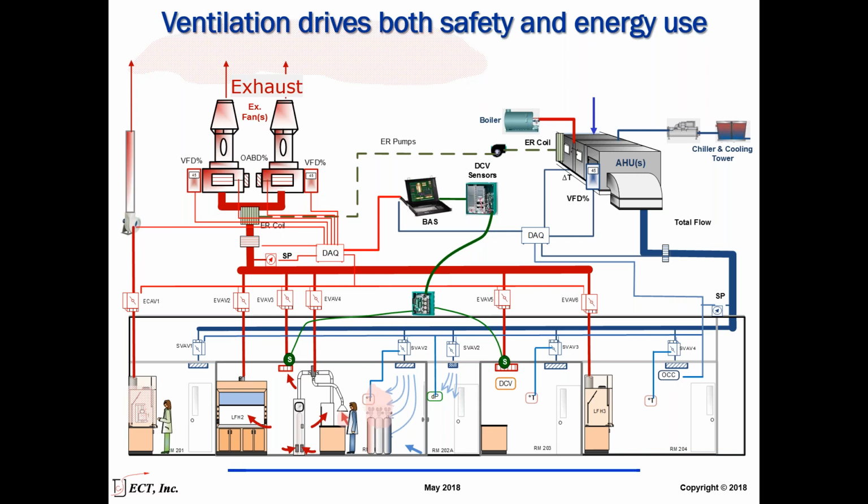The other 8,700 hours a year, you really don't have that condition where you really need 3,000 feet per minute. And so that's another consideration, especially if you have really high volumes. You may not need that. Again, it depends very much on the surroundings, what the buildings are around, what the weather conditions are, and the topography of where people would be and other things in the environment.